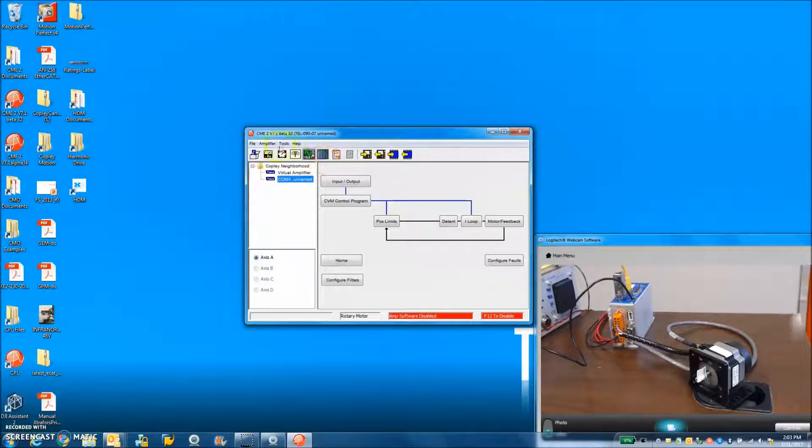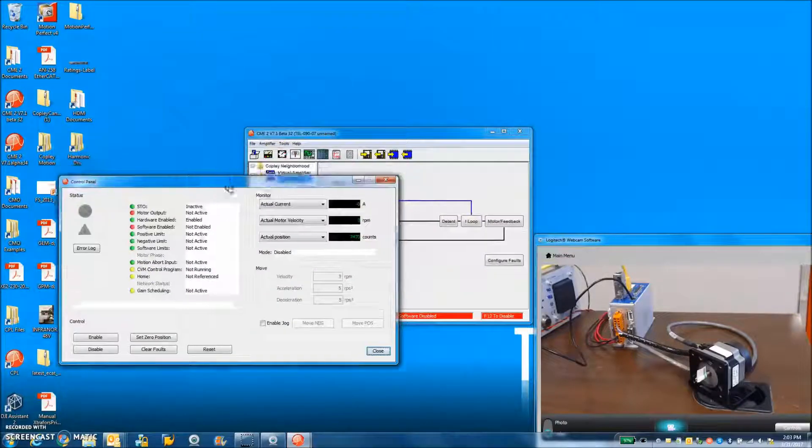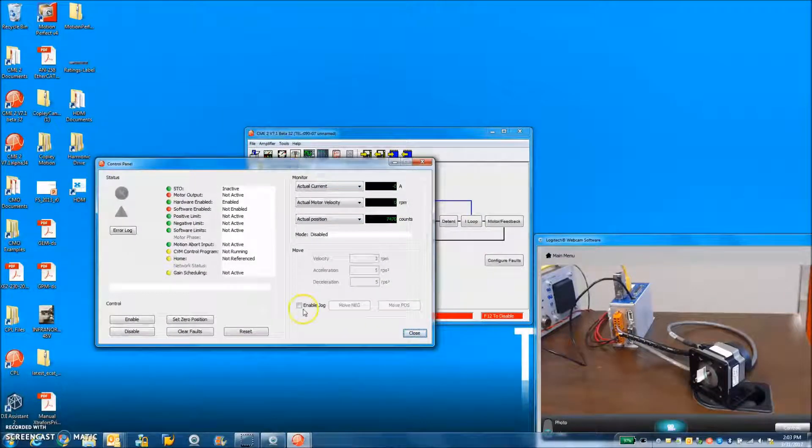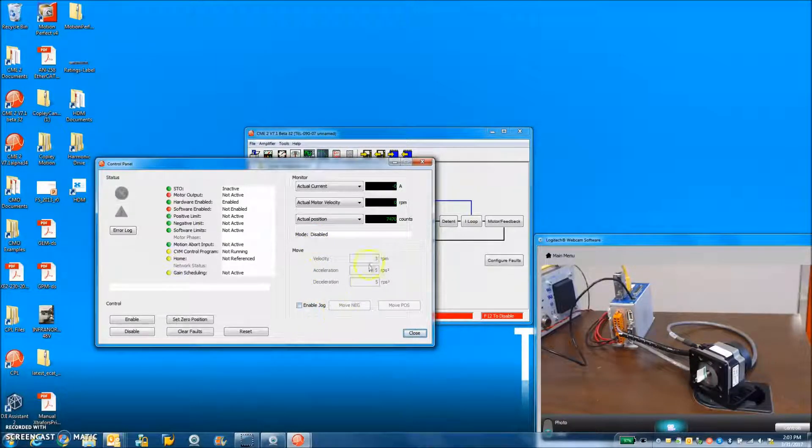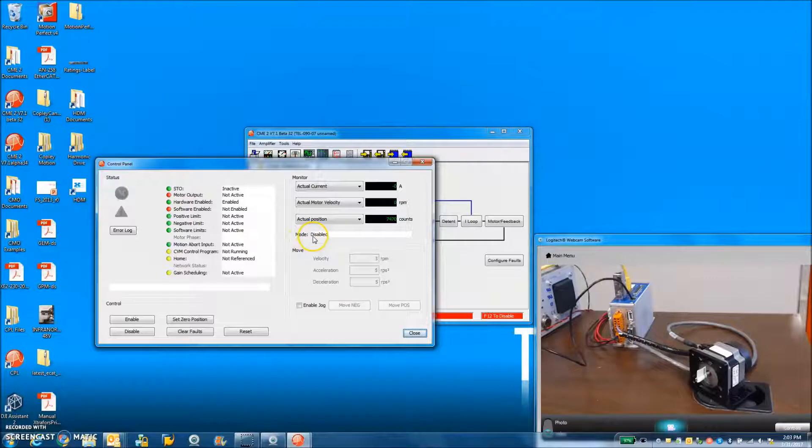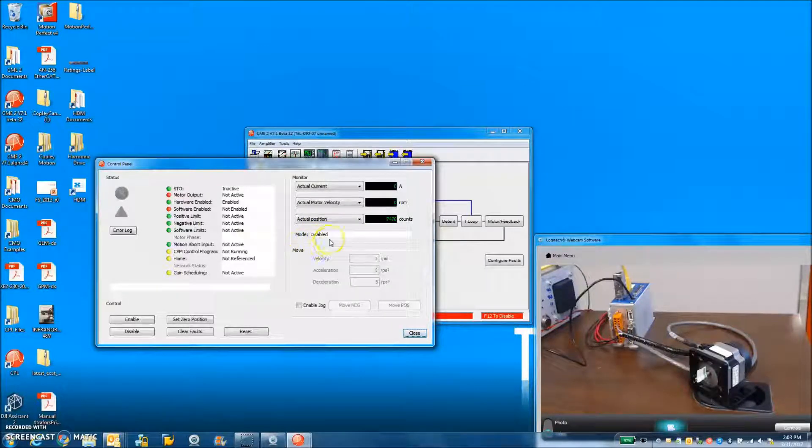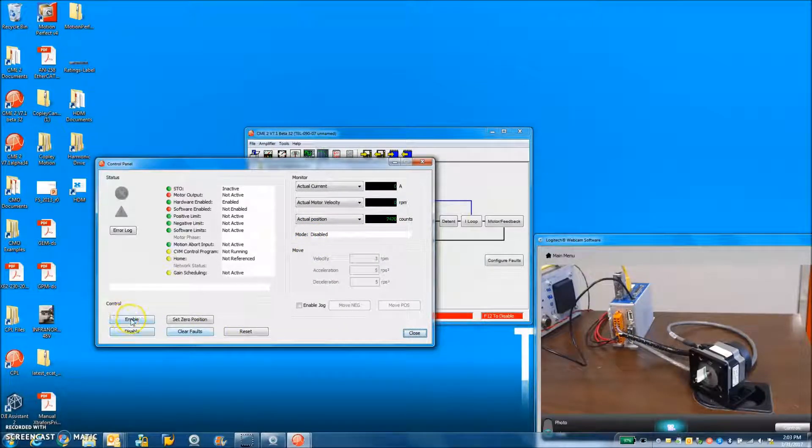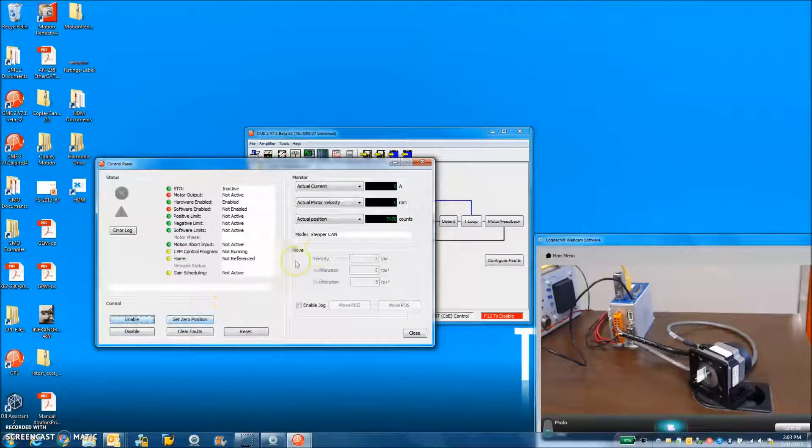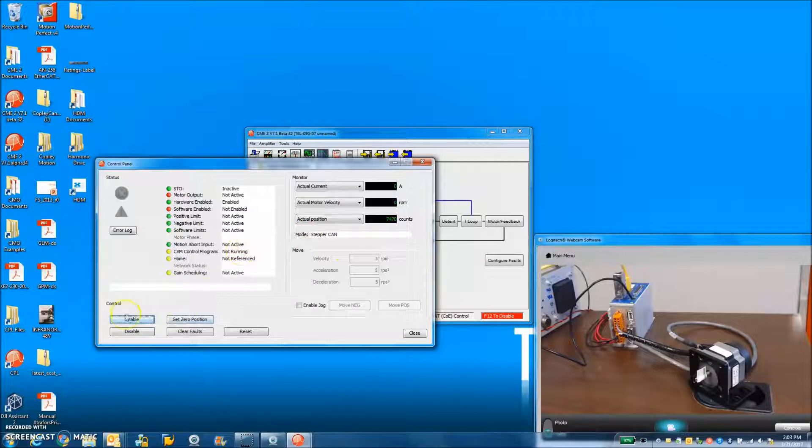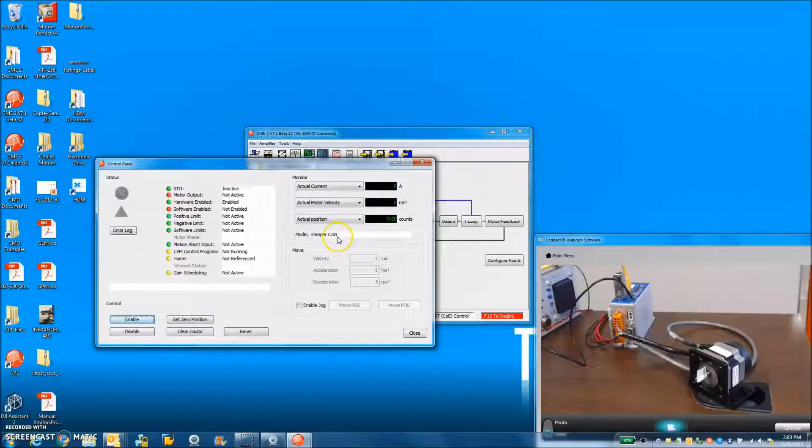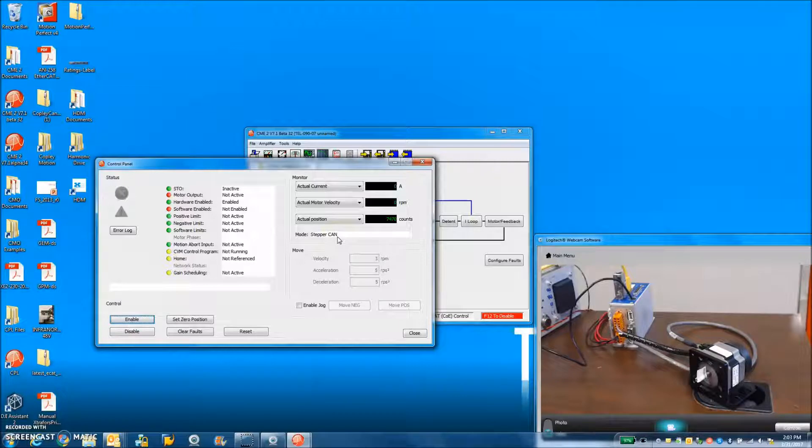We've got a little time here, so let's see how to configure this thing for the EtherCAT. Normally, we may want to jog the motor to check it out after our tuning, but we have to be careful. When we're disabled in this disabled mode, that's not the EtherCAT mode. On power up or reset, we'll be in the mode that's saved in flash. This is stepper can mode. It's EtherCAT. It's COE. That's why we call it stepper can.